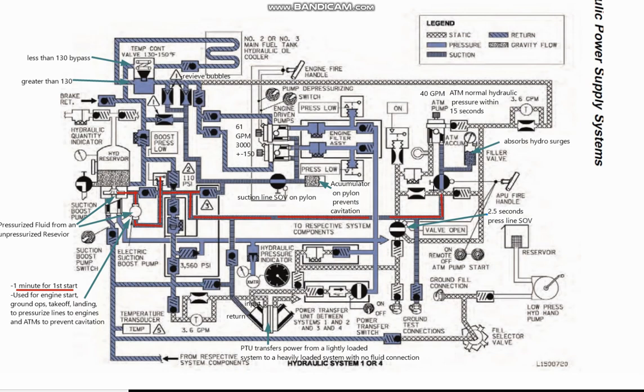Right now this valve is closed, kind of drawn as the system's running. Then we go back over here, it'll overcome this one-way check valve, make its way through our suction line shutoff valve, and provide pressure to the accumulator. The whole purpose of the accumulator is to prevent cavitation.